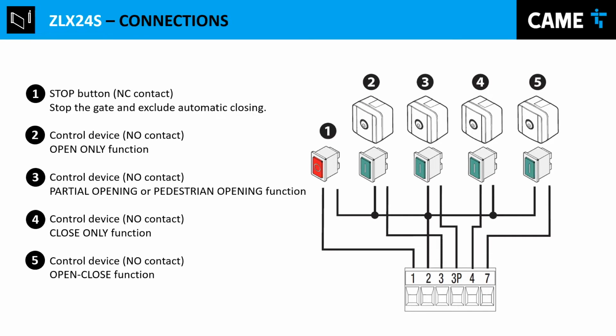The first one is total stop, that is normally closed - the only one that is normally closed contact, that's for safety. If you enable this, you need the contact to be closed. It's pin 1 and 2 - between pins 1 and 2, you need to leave that contact closed to get the operator working. If you open that contact, the operator is going to be disabled, basically it's not going to move. By default it comes disabled, so you don't need to worry about that.